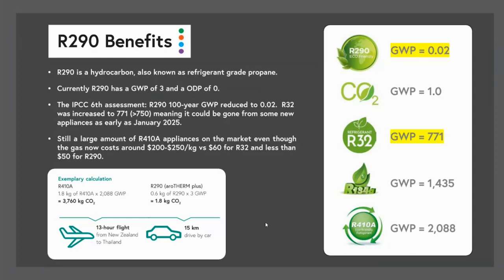And then you've got to question whether you should be replacing the appliance. Currently, it's around about $60 a kilo for R32 and less than $50 for R290. So R290 is in a very favorable position from a cost of the refrigerant point of view. Then looking at the bottom, there's a little calculation. It's an example of one heat pump compared to another and its carbon footprint.